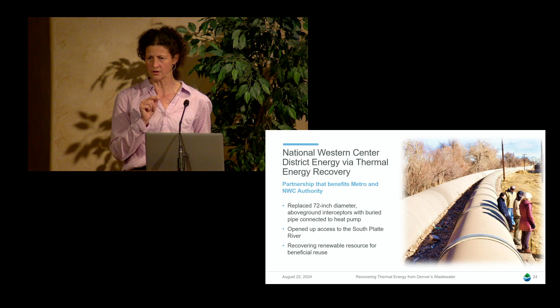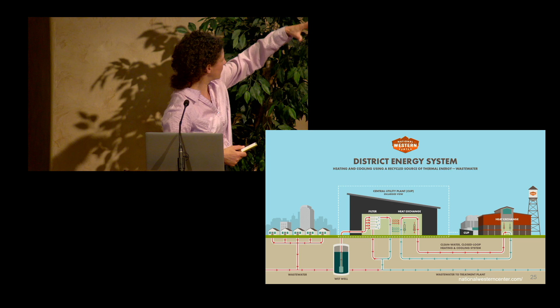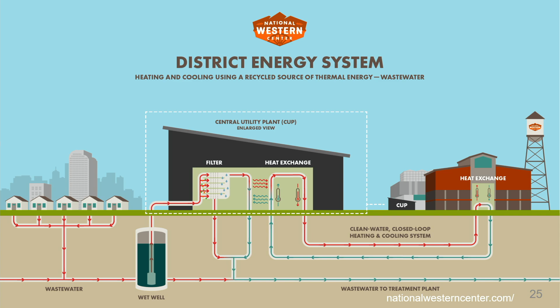Currently the capacity of that system is 4 megawatts, providing heating and cooling for those Spur buildings. Here's a schematic of that, very similar to what I showed you before. The City of Denver interceptor is providing wastewater, which contains heat. We have a wet well from which we are pumping the wastewater into a filter. It goes into a heat exchanger, the system I showed you before. That heat is put into an ambient heat loop, which in summertime carries cooler wastewater used in these four different buildings for cooling. In wintertime, we're providing hotter water in the ambient heat loop that is used in additional heat exchangers in each building to provide heat.